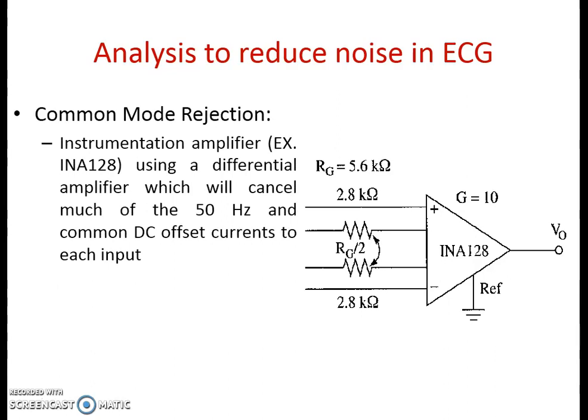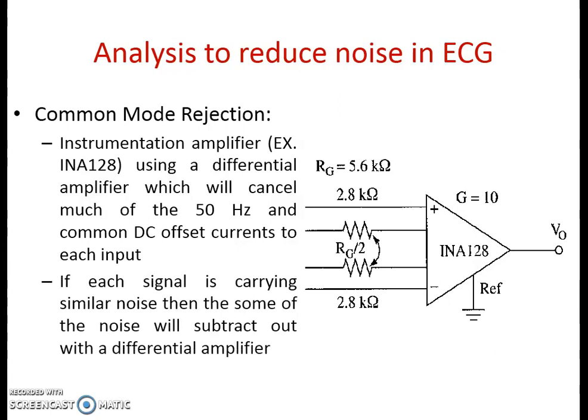By using an instrumentation amplifier which has a high CMRR — specifically we are using the INA128 circuit which gives high CMRR — this helps to reduce the 50 Hz noise as well as the common DC offsets. If each signal is carrying similar noise, the sum of the noise will subtract out with a differential configuration. The instrumentation amplifier generally has two stages: the first stage is known as the buffer stage while the second stage is called the differential amplifier. When the common mode signal appears the same at both terminals of the differential amplifier, it has the capability to reject this common mode signal and cancel this major source of error in the ECG preamplifier.